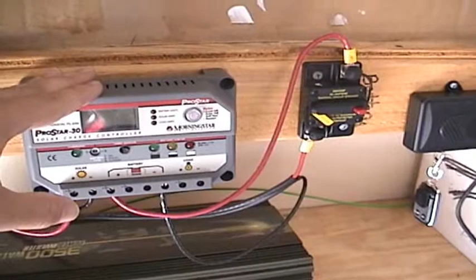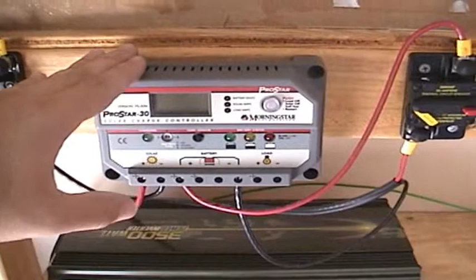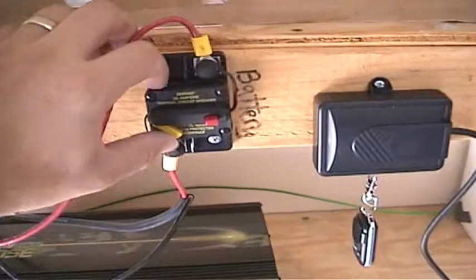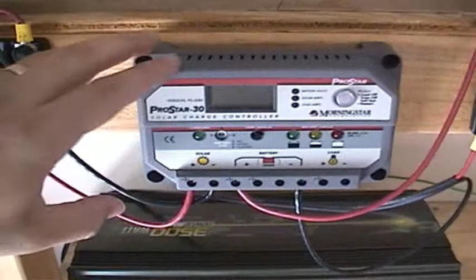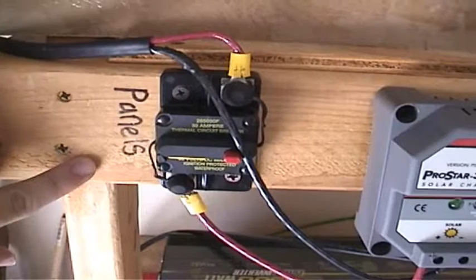Once you're done tinkering or fixing your system, you'll need to power it up again. The manufacturer of the solar charge controller recommends turning the battery circuit breaker on first before turning on the solar panel circuit breaker. Let's go ahead and do that now. We'll reset the little yellow tab on the battery circuit breaker—that will turn on the solar charge controller. Verify that it's on, then we can go ahead and reset the yellow tab on the panels circuit breaker.